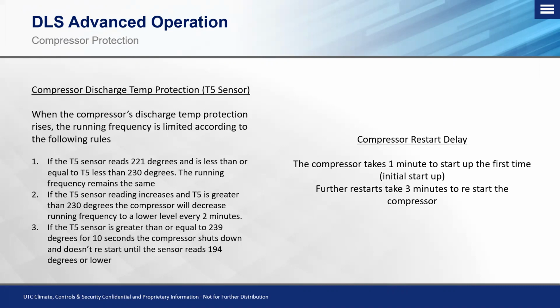So don't assume as soon as you turn something on that it's immediately going to fire off, especially if it just came out of a cycle, or if you cut power on the system to take some readings and then returning it back on to try to recycle the system to see how it's operating. Understand that there is a delay to protect that compressor, just like we have on a traditional style system.